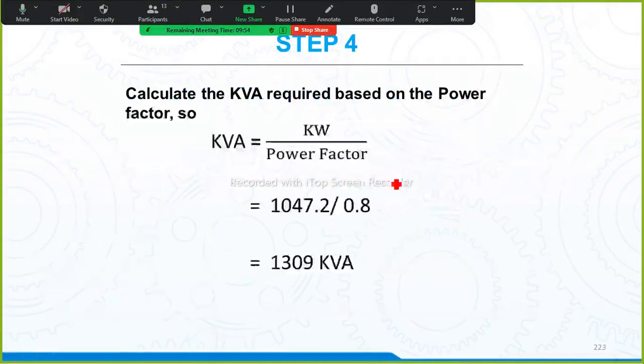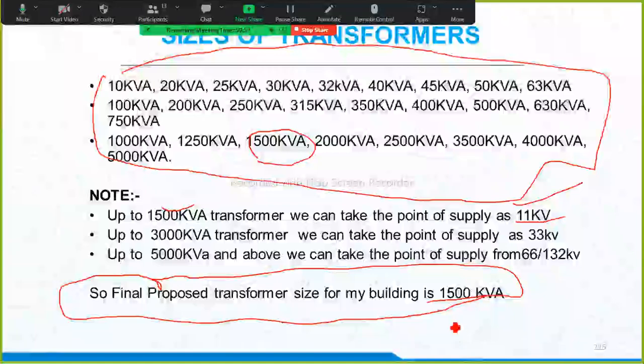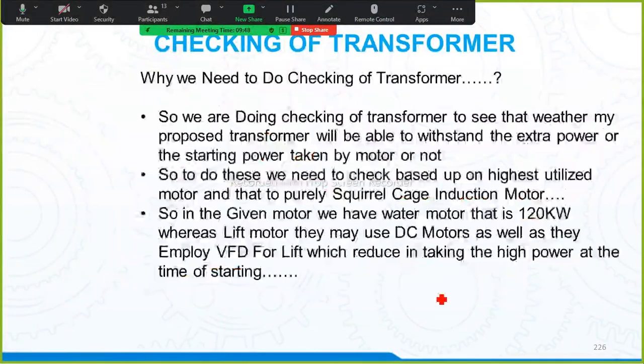Now we need to calculate, based upon this plumbing load, whether the 1500 kVA transformer I have installed is going to withstand that much power or not. Why do we need to check the transformer? We are checking to see whether my proposed transformer will be able to withstand the extra power, or the starting power, taken by the motor or not.